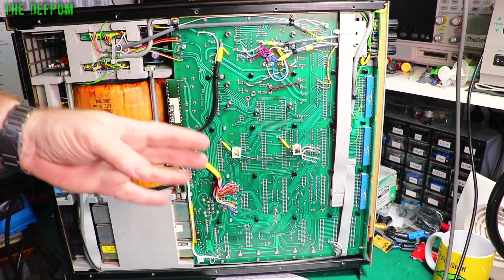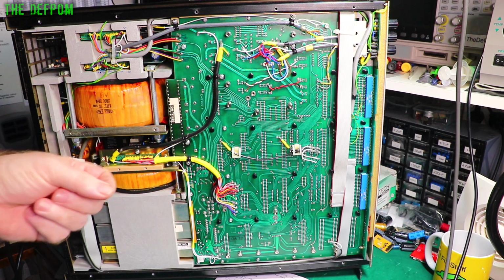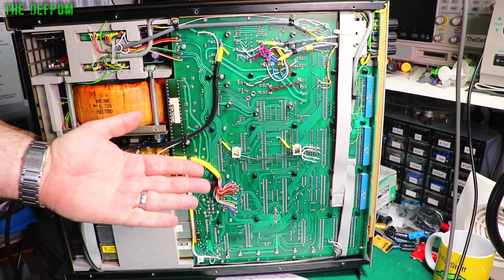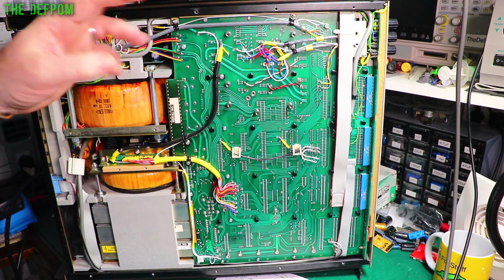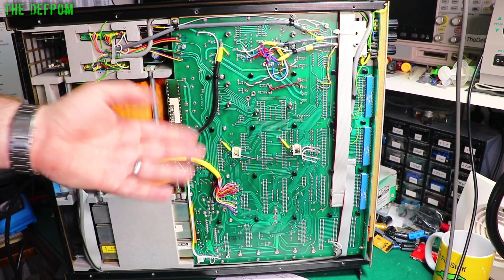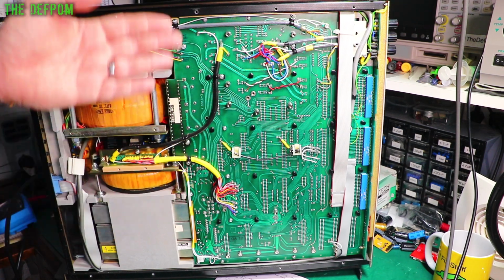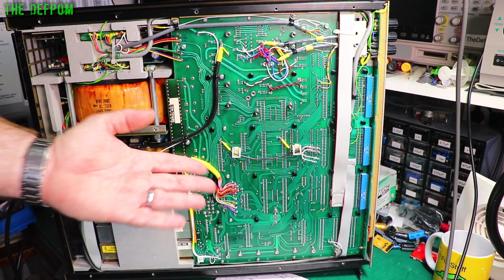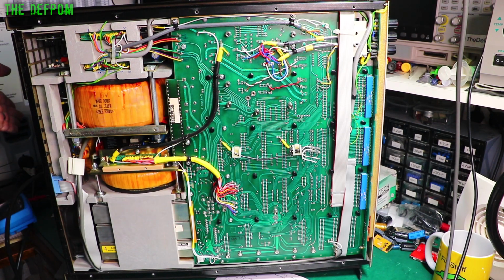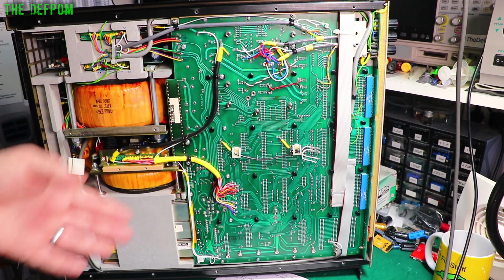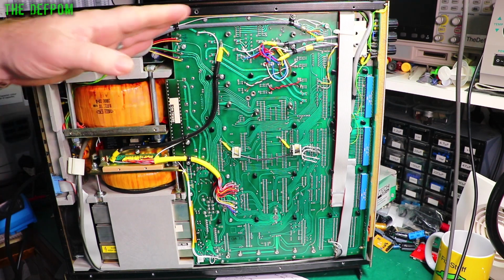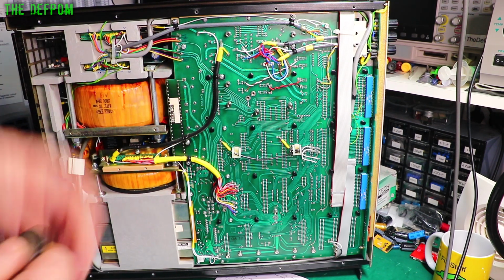Okay, so those power supplies probably don't matter because they're actually an unregulated supply. So it's purely a rectified supply, comes straight from a transformer. It's rectified, smoothed, and then sent out. There's no regulation on that 20 volt rail. Being 20 odd volts is going to be alright. My line input voltage is about 230 right now. It's set at 240 volt on the input jack on the back. It will be sitting slightly low, so it's probably fine, not worried about that.